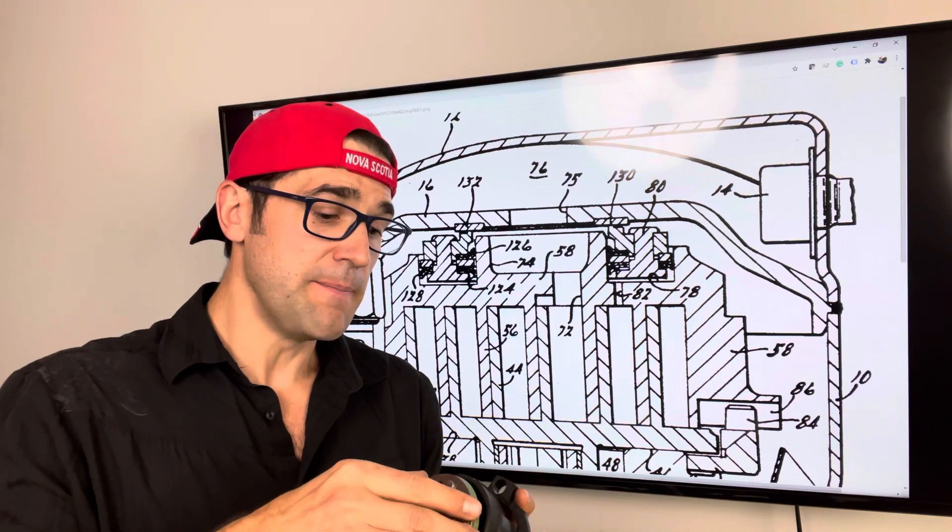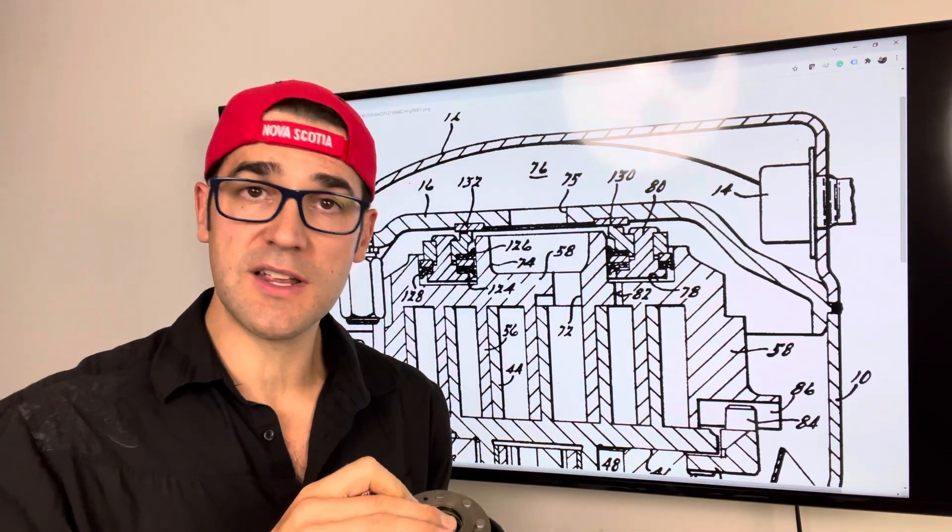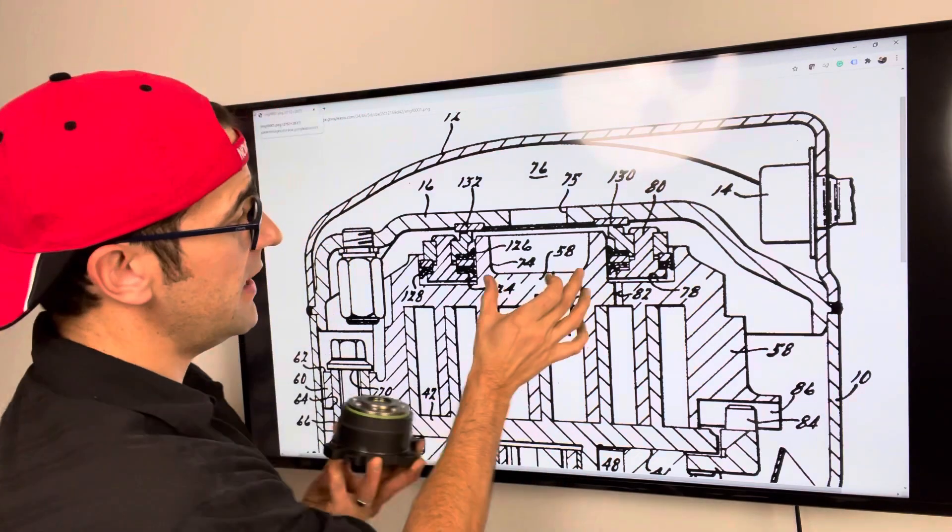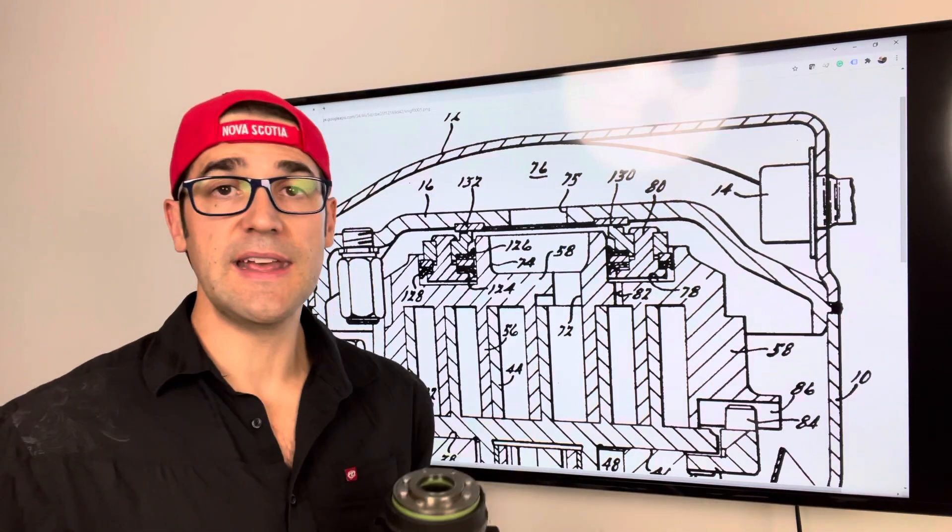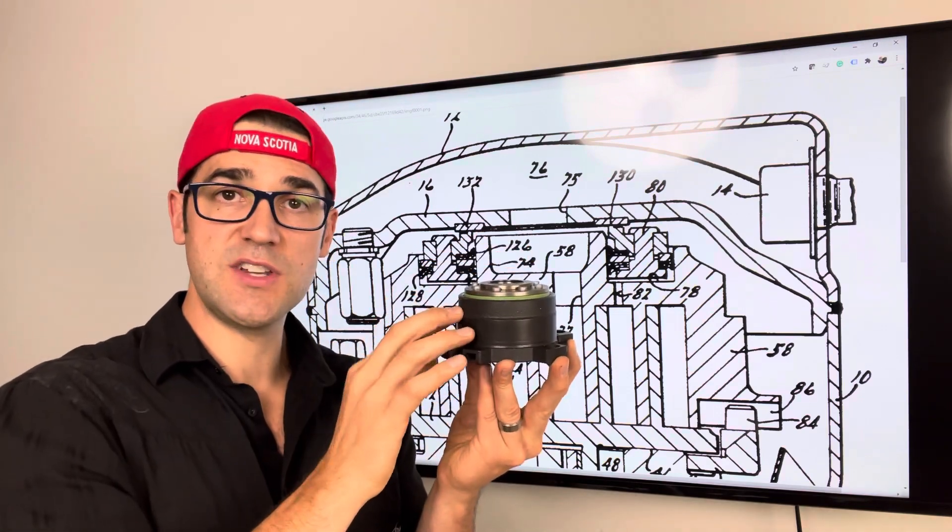You want to make sure that you wait for the compressor to cool down and check if it pumps again. If the floating seal here is ripped or damaged from overheat or contamination, this will not push up against the muffler plate.